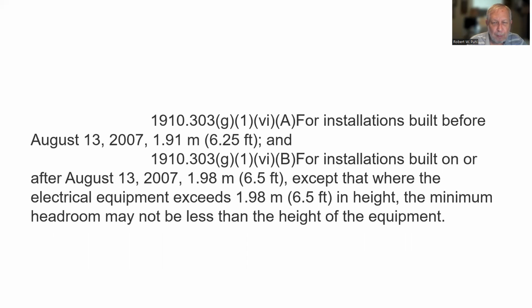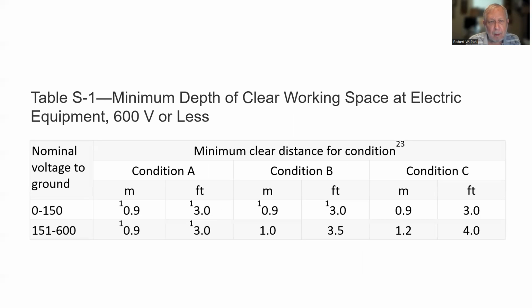For instance, built before 2007, 6.25 feet. After that, 6.5 feet. Except that where the electrical equipment exceeds 6.5 feet in height, the minimum headroom may not be less than the height of the equipment. Minimum depth of clear working space at electric equipment, 600 volts or less.